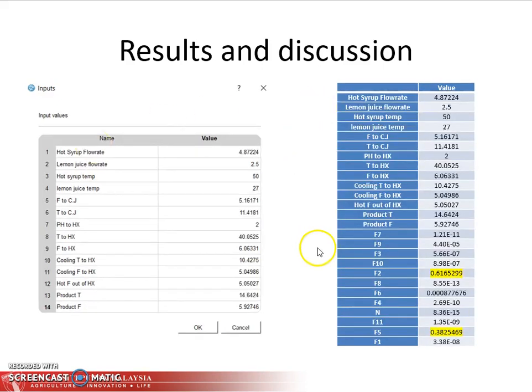The second trial, I tried to introduce two faults. I decreased the value of the heater, and I increased the value of the flow rate of the lemon juice. As you can see, the system detected a 0.61 probability for the flow rate change and 0.38 for the syrup heater, while giving very minimal values to the rest. So it actually just suggested to the operator that these two are having abnormalities in the operation.